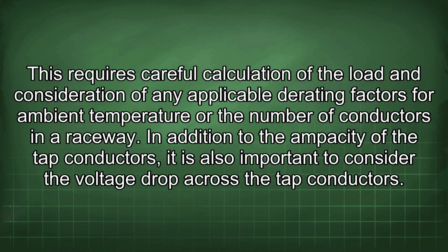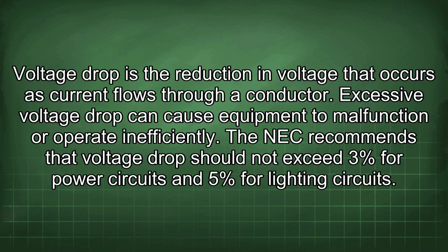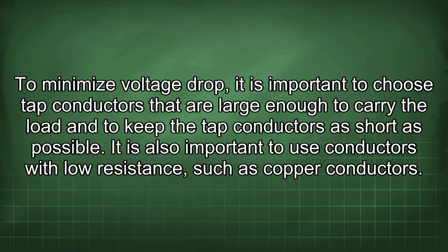In addition to the ampacity of the tap conductors, it is also important to consider the voltage drop across the tap conductors. Voltage drop is the reduction in voltage that occurs as current flows through a conductor. Excessive voltage drop can cause equipment to malfunction or operate inefficiently. The NEC recommends that voltage drop should not exceed 3% for power circuits and 5% for lighting circuits. To minimize voltage drop, it is important to choose tap conductors that are large enough to carry the load and to keep the tap conductors as short as possible. It is also important to use conductors with low resistance, such as copper conductors.